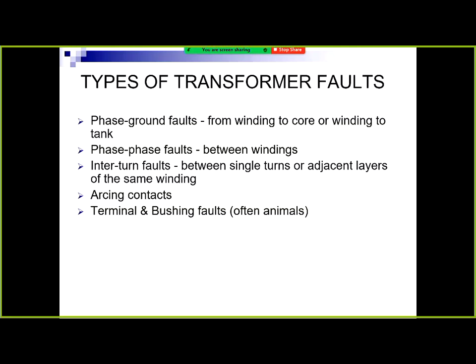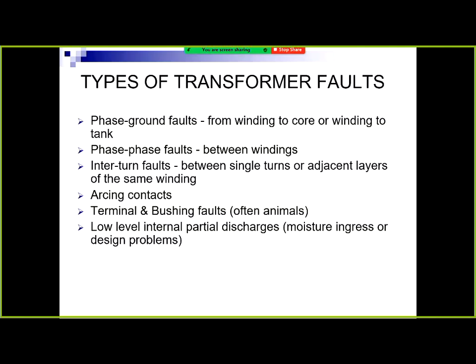I've heard a few over the years where a snake has got in winter, curled around the 33 kV windings to warm up and tripped the transformer, and they find a dead snake when they go out there. Clean it out, test the transformer and put it hopefully back into service without damage. Usually it's not damaged, they can put it back in, but we have to monitor it as well. Partial discharge, which can be moisture getting into the transformer, which is a design problem.